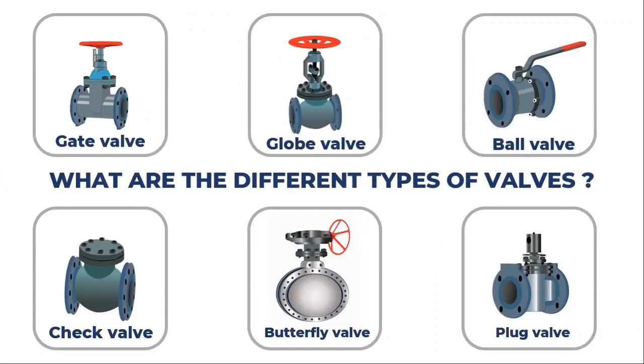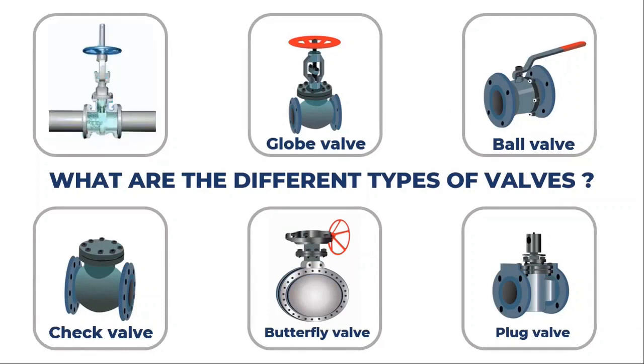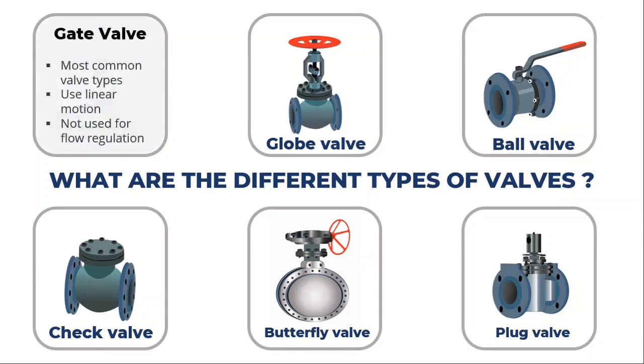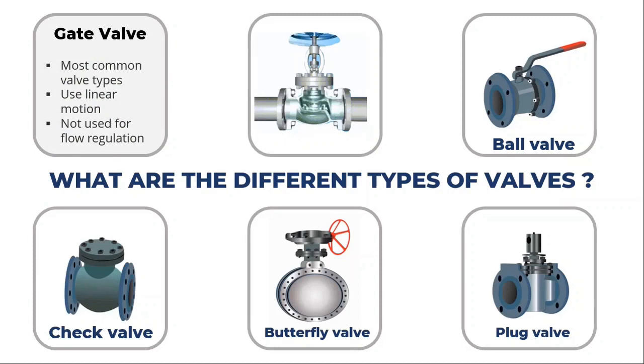The most frequently used valve types are gate valves, globe valves, ball valves, check valves, butterfly valves, and plug valves. The most popular kind of valve seen in process facilities is the gate valve. A linear path is followed by the closing gate to either obstruct or let fluid pass. Usually they are not utilized to control flow — instead they are utilized in the fully open or closed states.